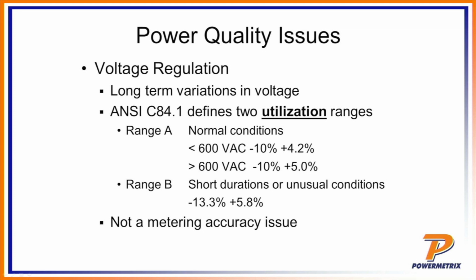If we talk about the utilization range, utilization is basically where the customers plug into the wall, and so what you'll see there is, once again, you're giving a little bit more leeway from the service entrance. For less than 600 volts, you can go down to as much as minus 10% or as much as plus 4.2%. So once again, the equipment is designed to those sort of ranges. It will be much more forgiving if we have a sag as opposed to a swell, just because that's the way that it's specified, that's the way it's going to be designed. Once again, the short durations, we can have up to minus 13% or plus 5.8%. Yet once again, metering actually is not an issue because the meter will average that and there won't be a problem.